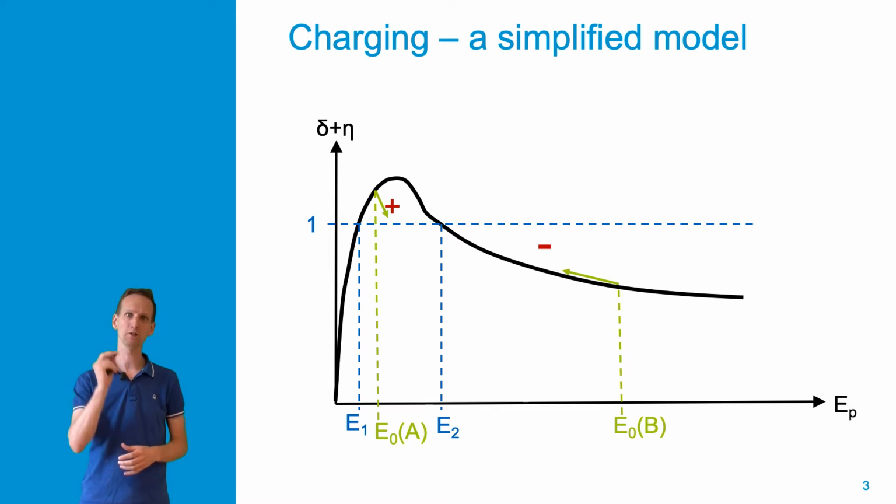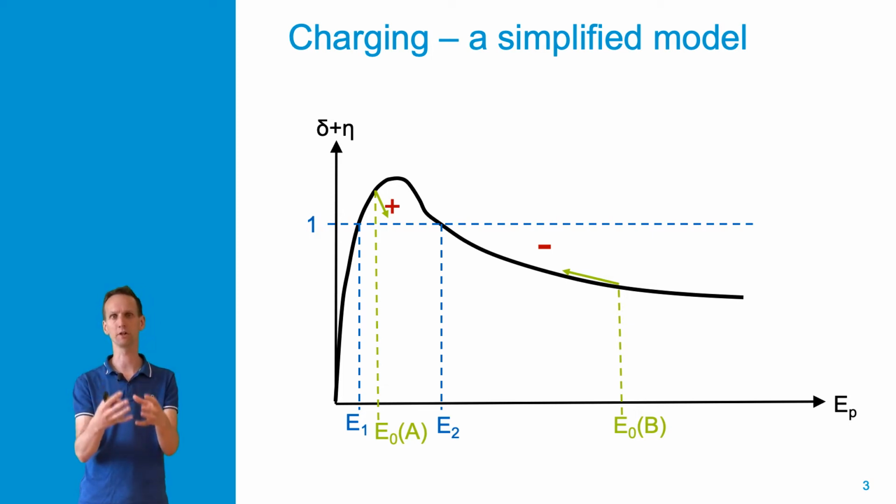Now we should realize that if a sample is conductive, this is not a problem, because there will be a current through the sample to ground, which compensates for this charge buildup. Also, if the sample is insulating but covered by a conductor, we will have this charge buildup, but the covering conductive layer will work as a Faraday cage, shielding the incoming primary beam from the effect of the charge buildup below. However, if this is not the case, this charge buildup may lead to a deviation of the electron beam resulting from the electric field generated by the buildup charge.